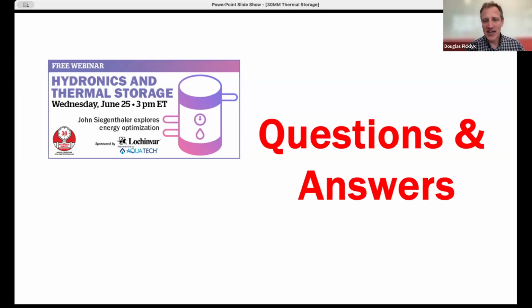One person's asking, how does a designer correlate heat pump flow rates and minimum cycle times to buffer tank sizing so as to utilize stratification rather than mixing the whole buffer tank? That's a good question, but I can't give you a short answer on that. The best thing I can tell you is look at the tank, and if you're trying to maintain stratification in the tank, with horizontal flow, you might go to larger inlet sizes on the tank to slow the flow velocity down as it comes in.